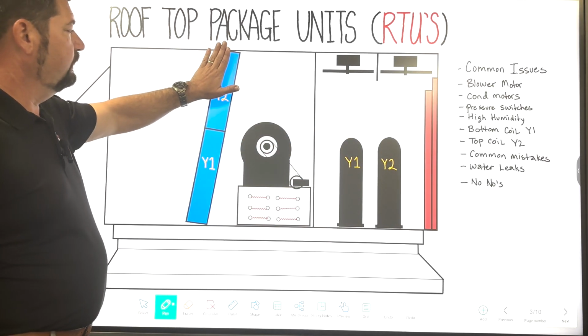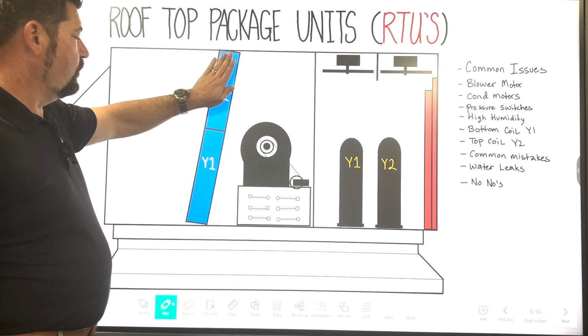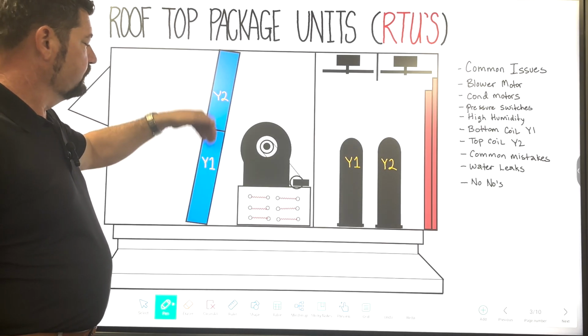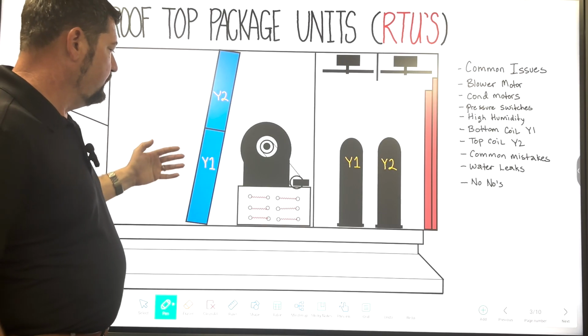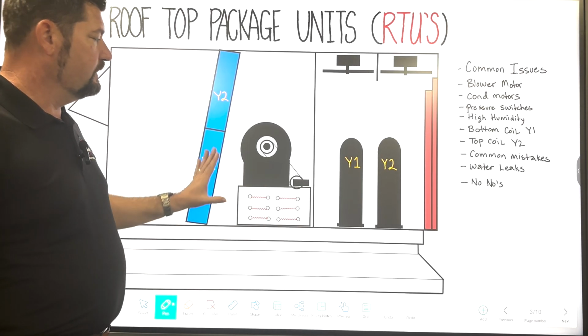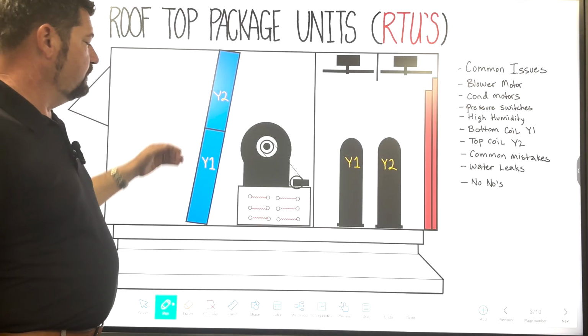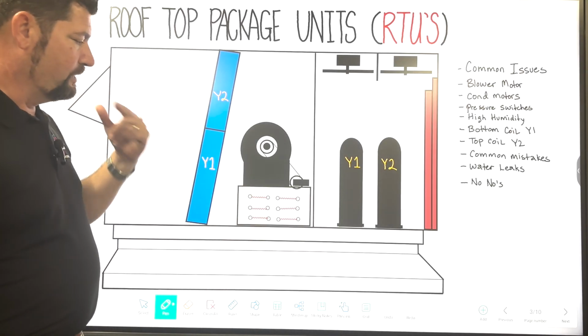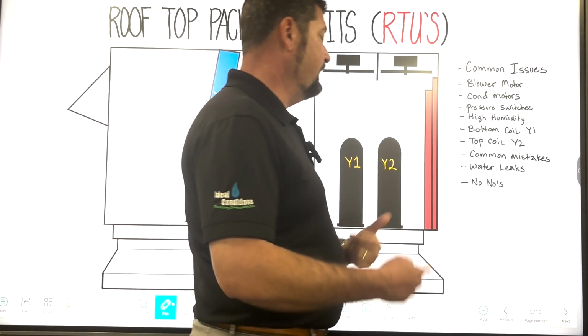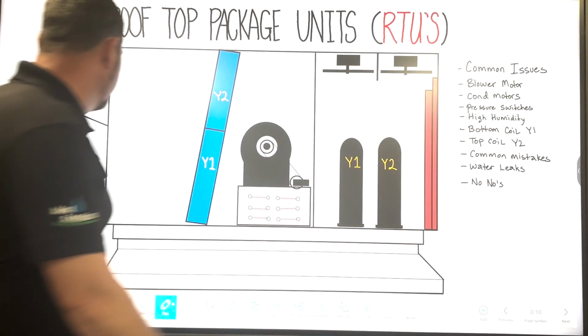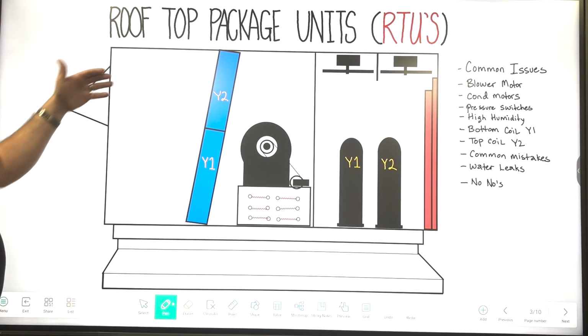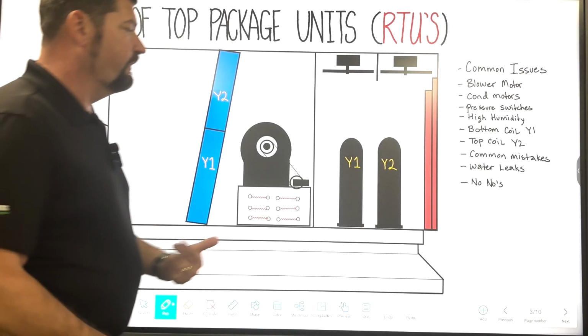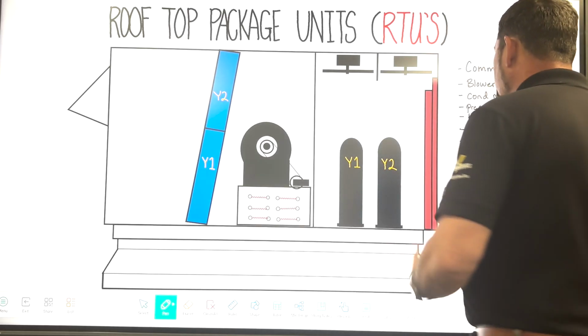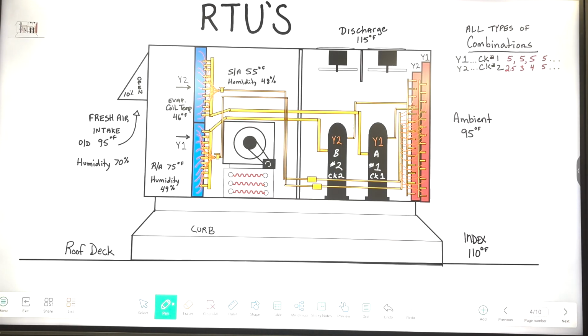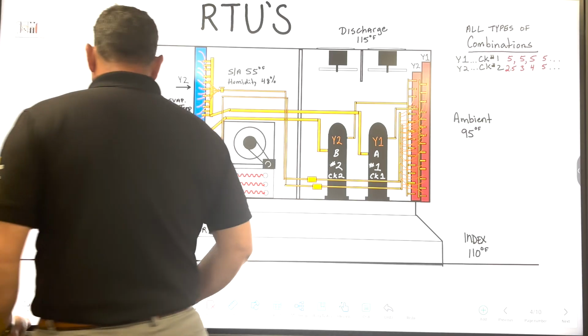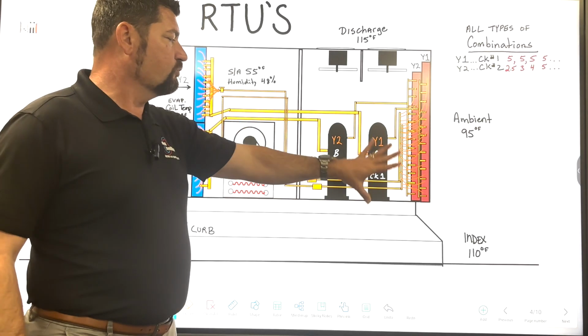then that humidity that is being removed by that coil being cold, this coil being warm, that water is just going to run down into it and that blower is just going to pull it right off of there, and the dehumidification is going to be rehumidifying the air. So you're not going to have an absence of moisture. You're not going to be doing anything with that moisture. So as we add more moisture in here, even if it's a low percentage to the building, there's no way to really dehumidify that in that situation. So we could have a high humidity issue. I'm going to get into a more elaborate description of what we just went through.